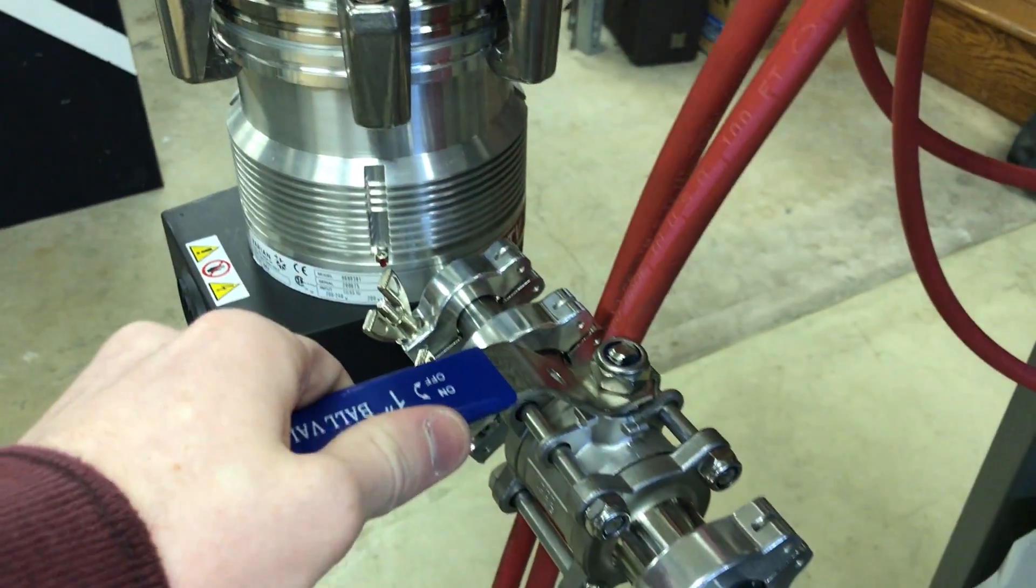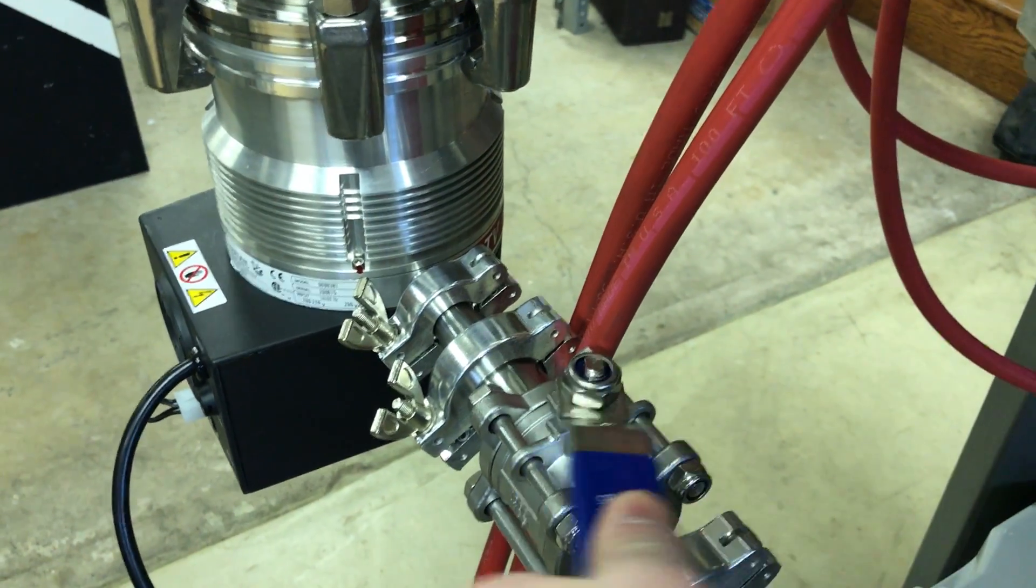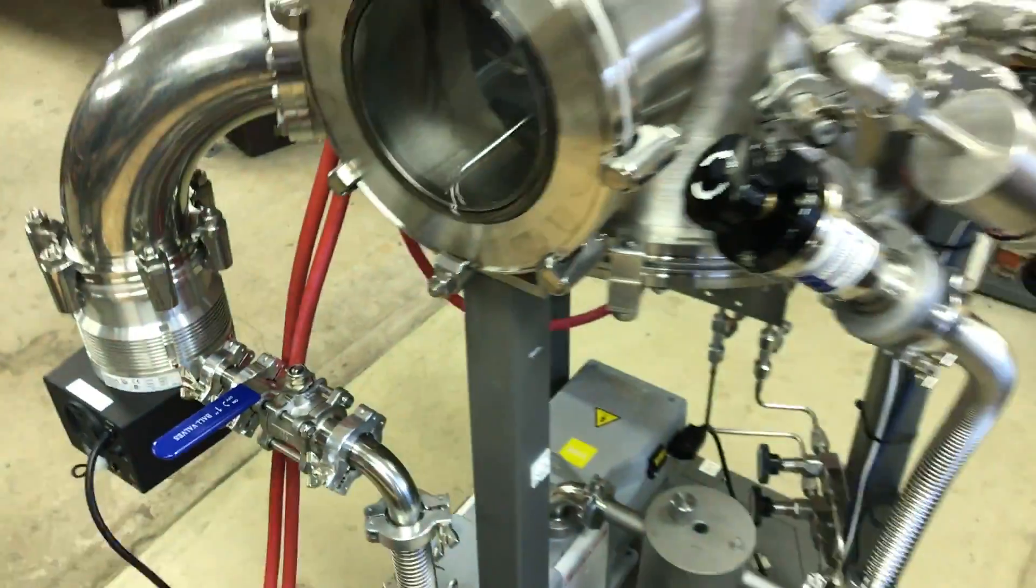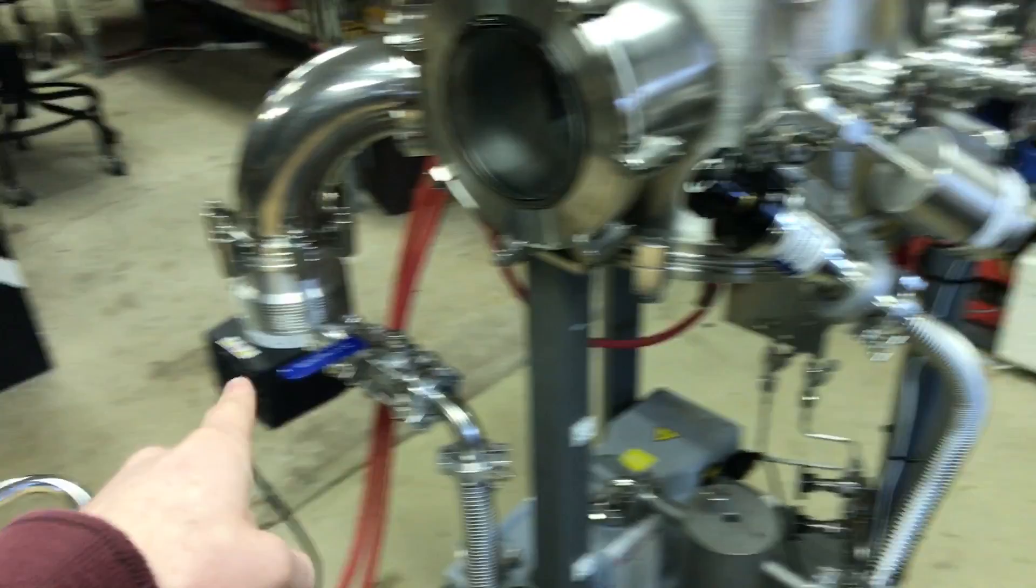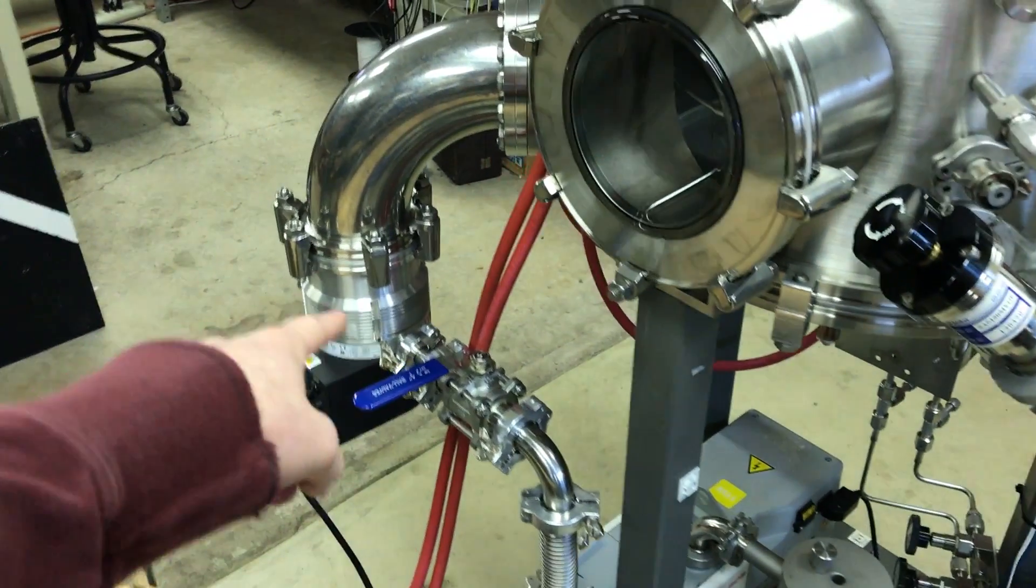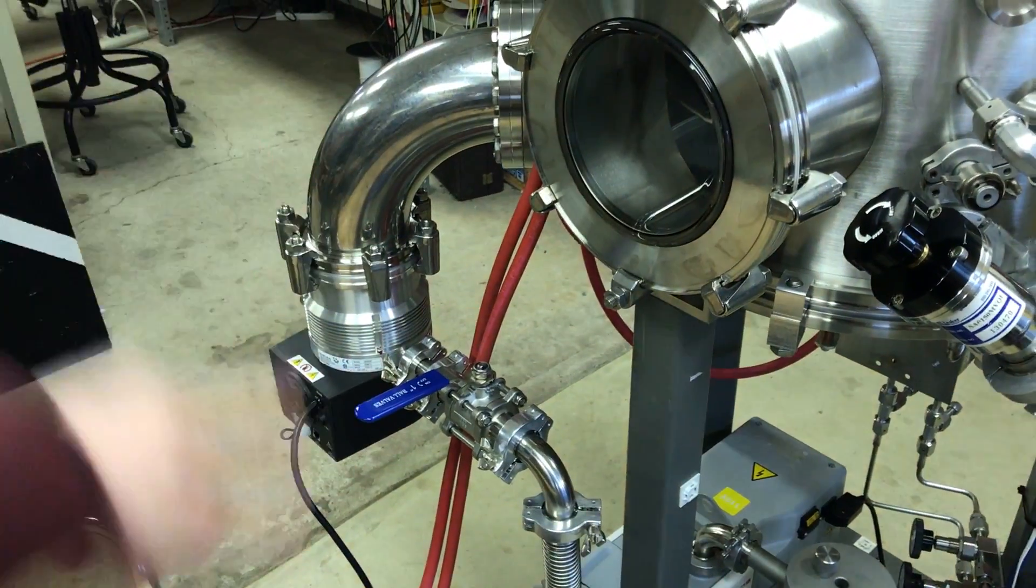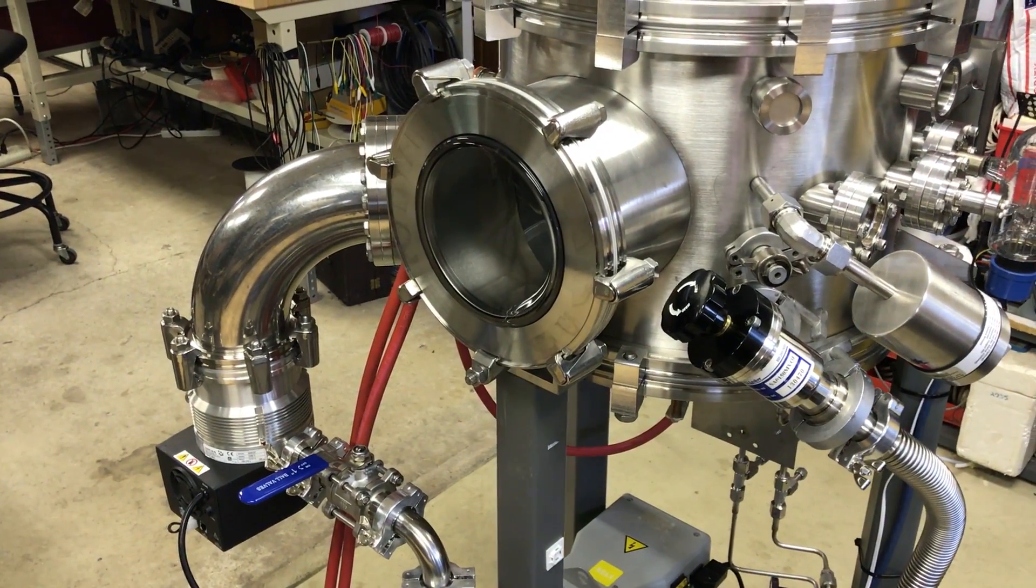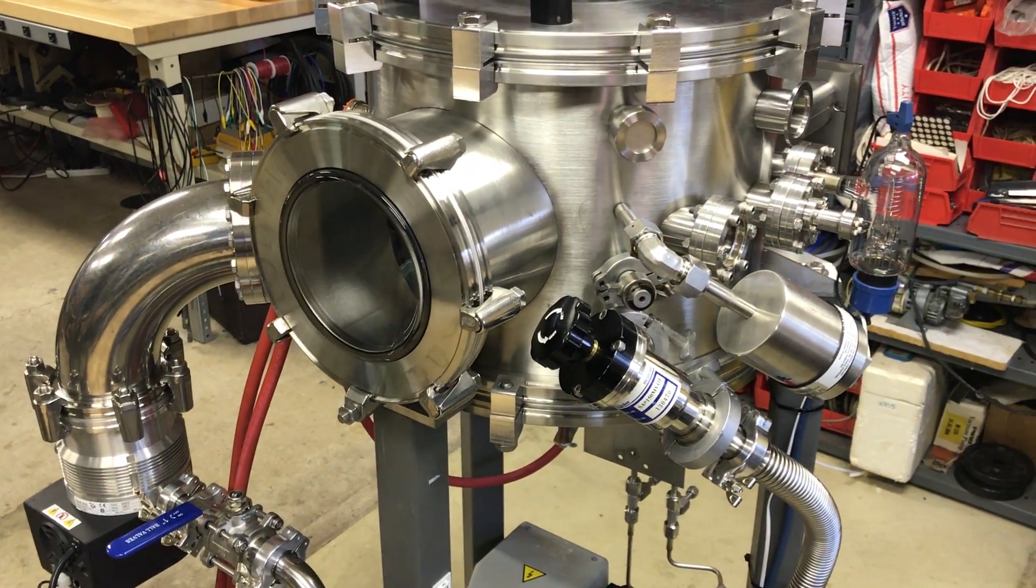So for the turbo pump to work effectively, we have to have this backing assembly. So I have the KF-25 hose through an elbow, and then this is just a valve, isolation valve, and then this goes to the backing port of the turbo. So once the chamber is pumped down, I close that valve, open the backing line, and then I pull through the turbo and spin up the turbo, etc.